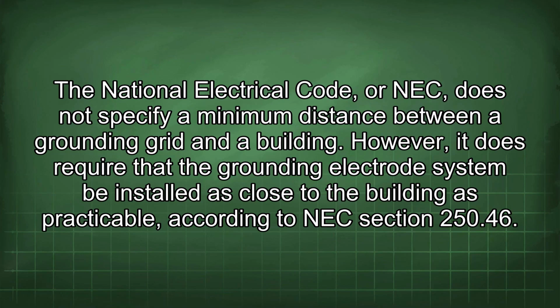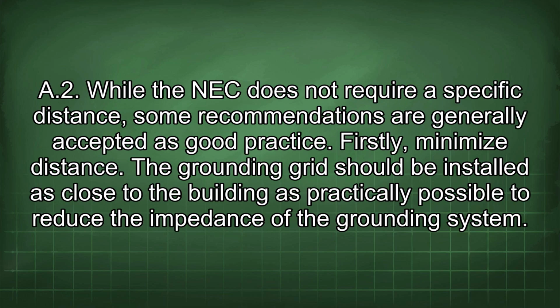The National Electrical Code, or NEC, does not specify a minimum distance between a grounding grid and a building. However, it does require that the grounding electrode system be installed as close to the building as practicable, according to NEC section 250.46. A2. While the NEC does not require a specific distance, some recommendations are generally accepted as good practice.